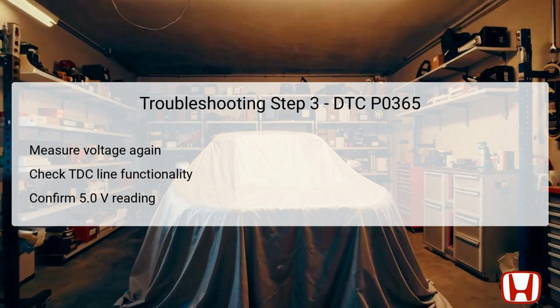The goal is to confirm if the voltage reading approaches approximately 5.0 volts, which is indicative of correct voltage levels for sensor operation. Receiving a valid measurement of around 5V implies that the TDC wire is functional, leading you to advance to step 4. However, if the reading is not close to this voltage level, it suggests further investigation is needed into wiring faults, prompting a move to step 5.